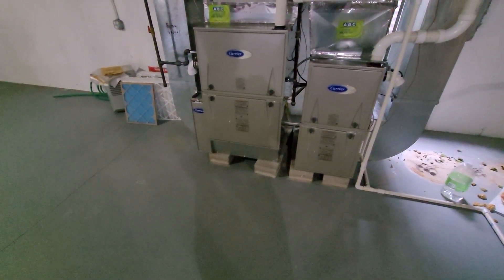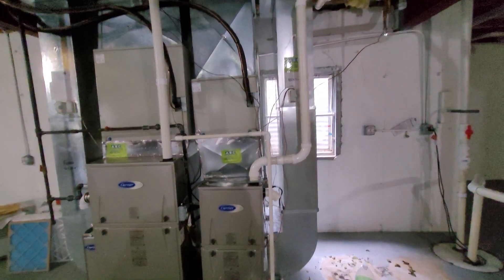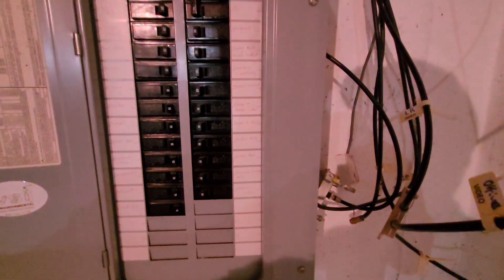Humidifiers on both and independent returns on both. Electrical is over in the corner and that appears to be a GE box — Cutler Hammer GE, yep. We've got a 40 and a 20 for the ACs, so we are in good shape. It's Aaron 851 — call with any questions.